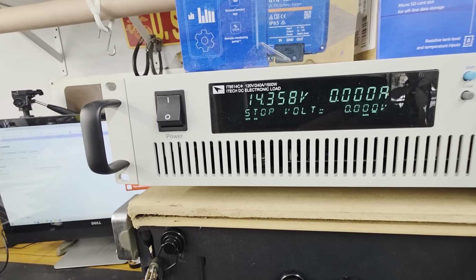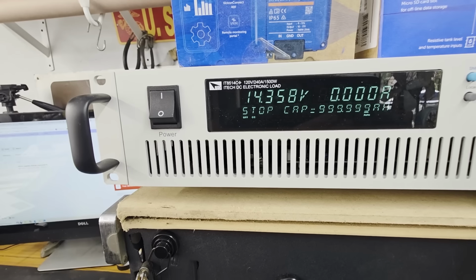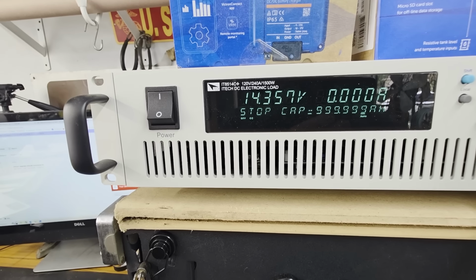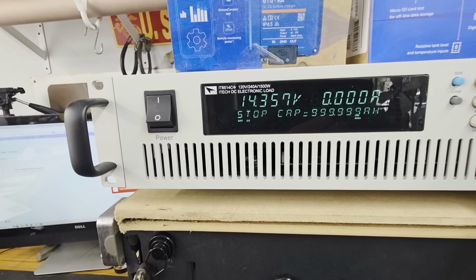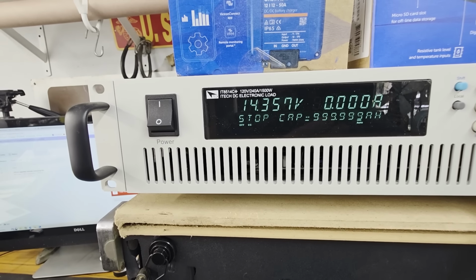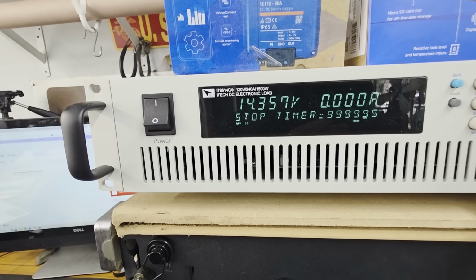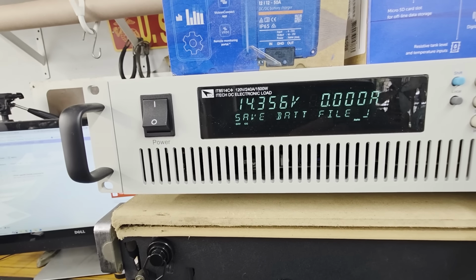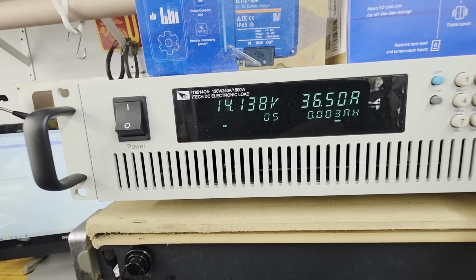Stop volts is set to 0 because the BMS is going to do the stopping. Capacity is set to 999, exceedingly high, again because the voltage and the BMS will do the stopping of this test. Timer is exceedingly long. Save the battery file and turn it on.